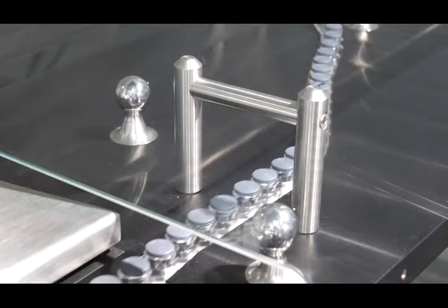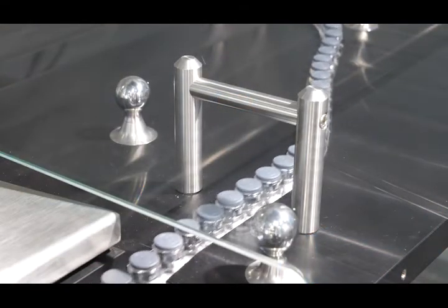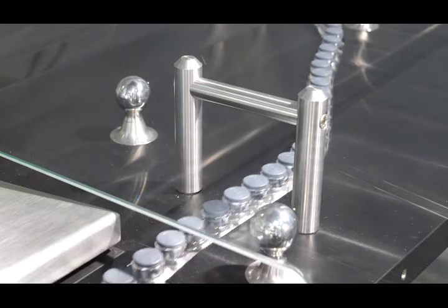Today I would like to show you our LYOSENSE software. The LYOSENSE software is a fast and effective application for real-time moisture detection. The software is based on multipoint NIR technology and is a non-destructive way to evaluate your freeze-dried products in real-time. For GEA freeze dryers with automatic loading and unloading system using LYOSENSE, we developed a special software and SCADA evaluation for a higher customer benefit.